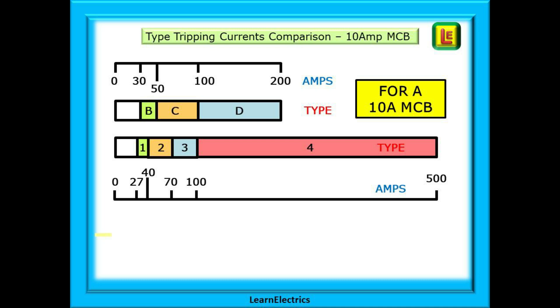For a C type the same 10 amp MCB will think about tripping with a fault current between 50 and 100 amps. At 100 amps it will definitely have tripped. That is to say 10 times 10 amps is 100 amps. And the 10 amp D type between 100 and 200 amps. 10 amps times 20 is 200 amps.